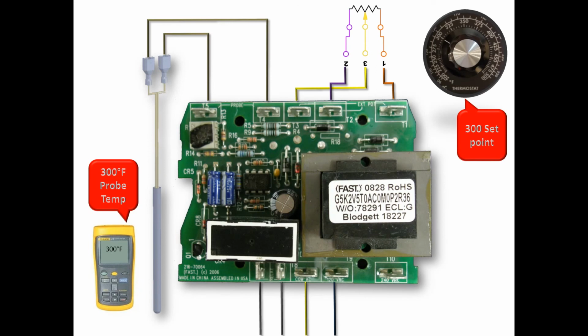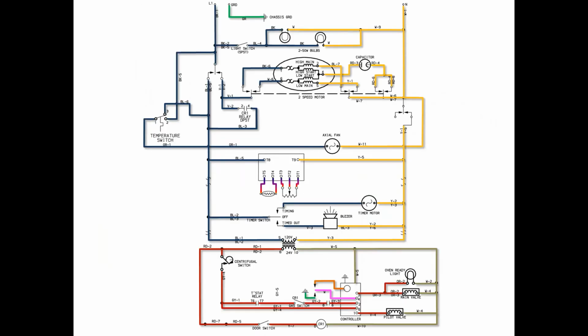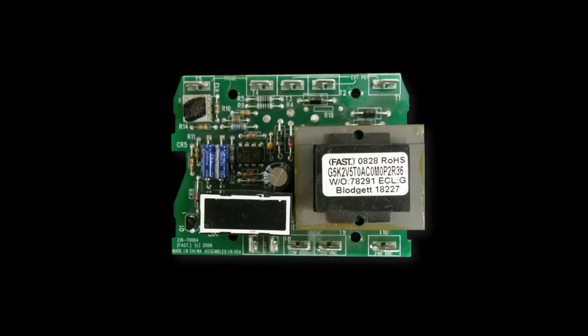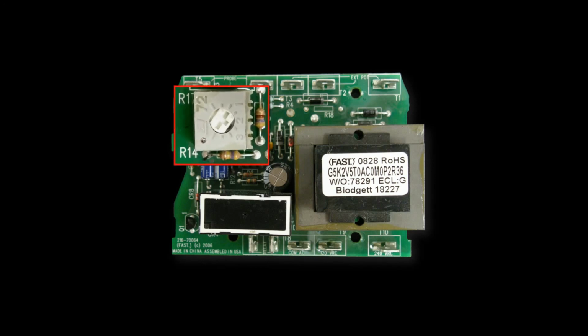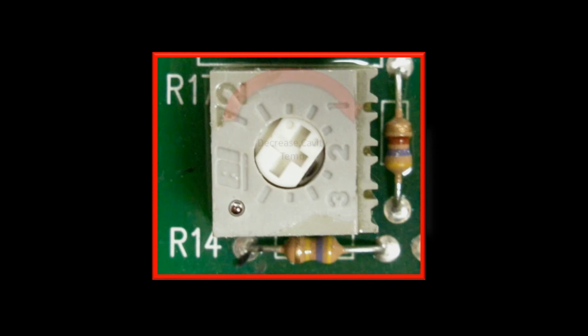When the unit reaches set point, the call for heat ends. Here we see the call for heat ending on the diagram when the probe shows that the set point has been reached. If the oven requires calibration, the potentiometer shown here can be used. Refer to the service manual for the calibration procedure.